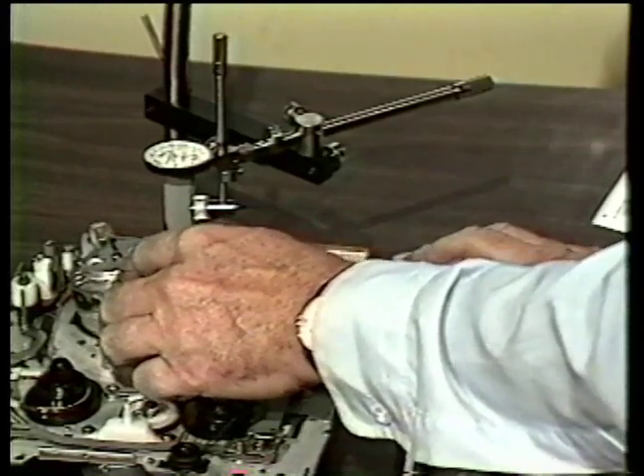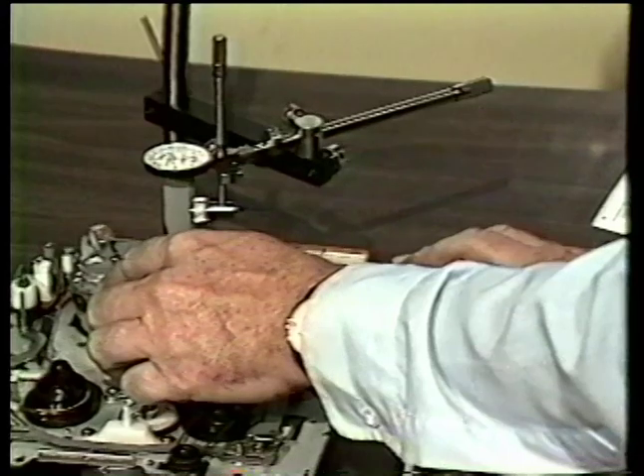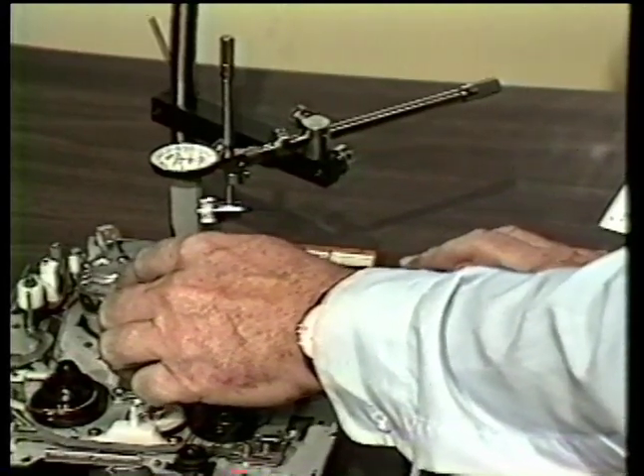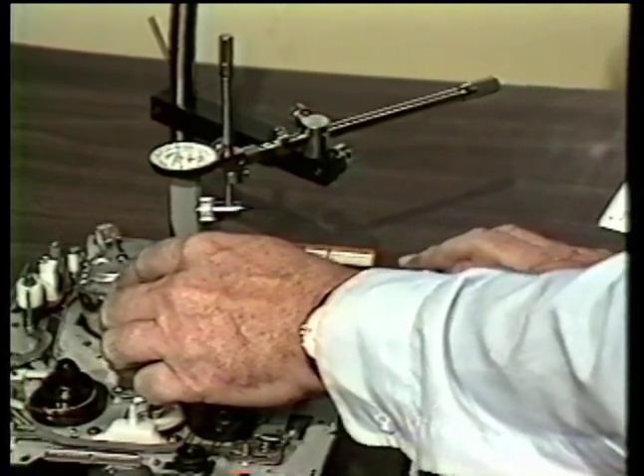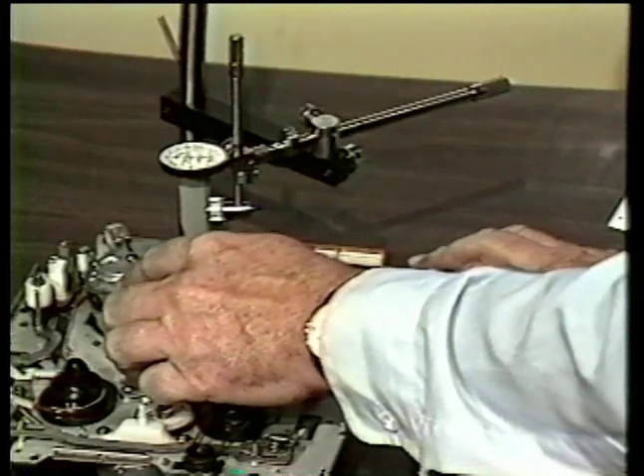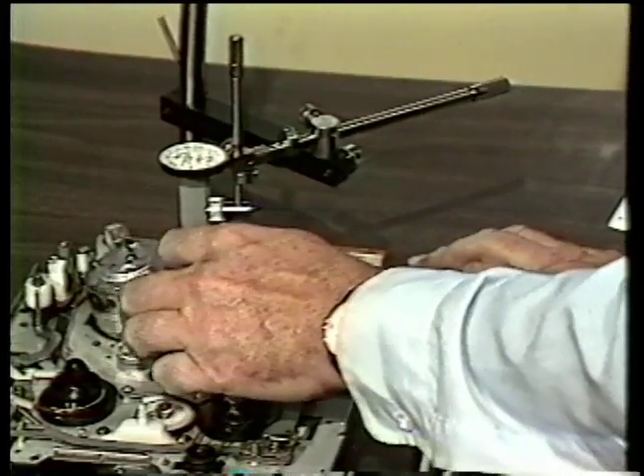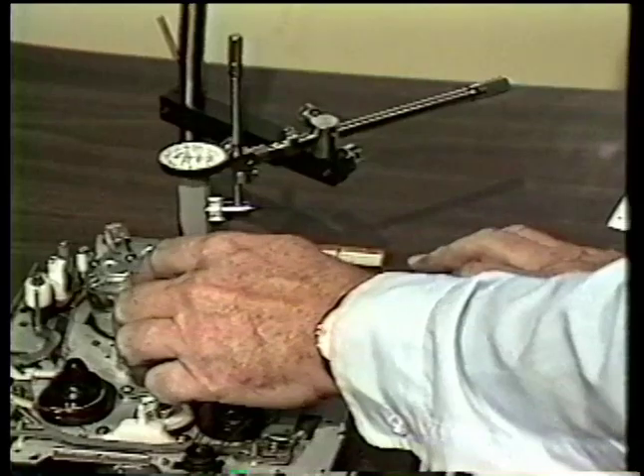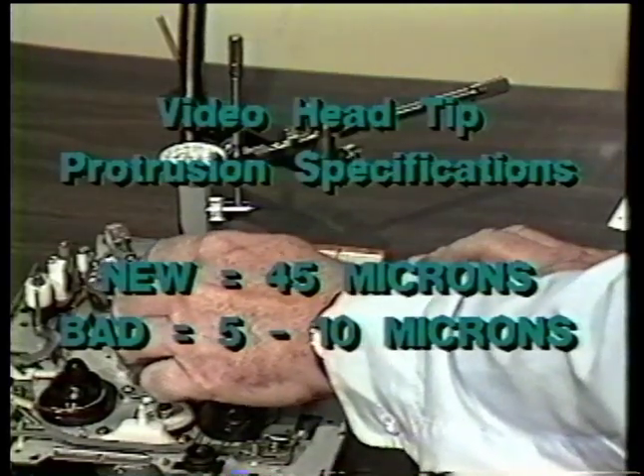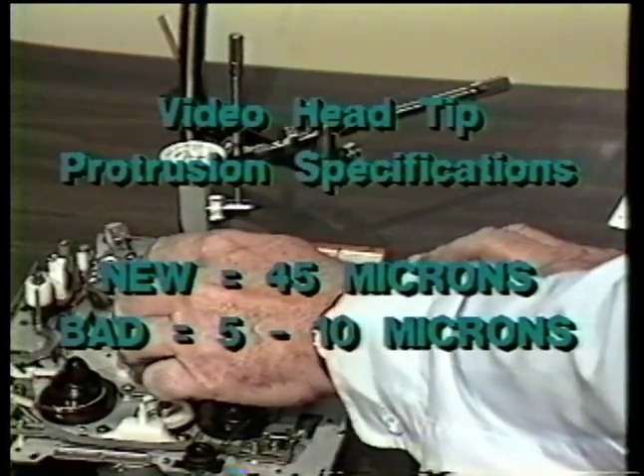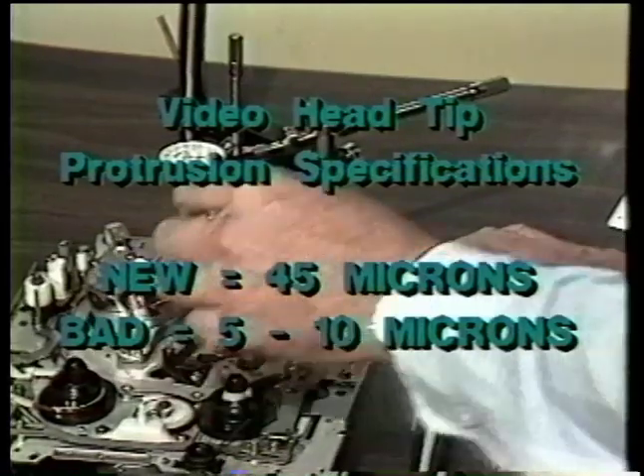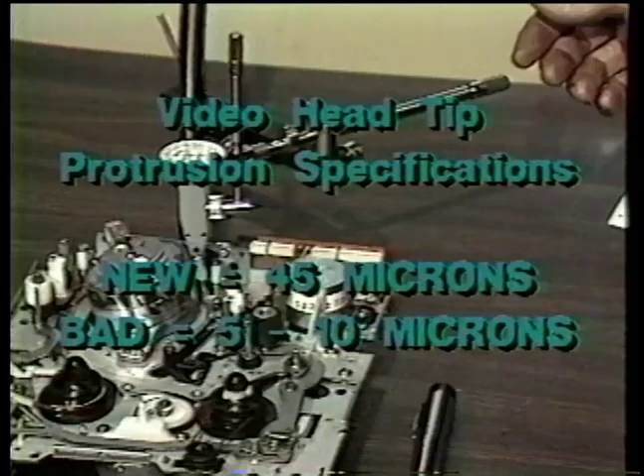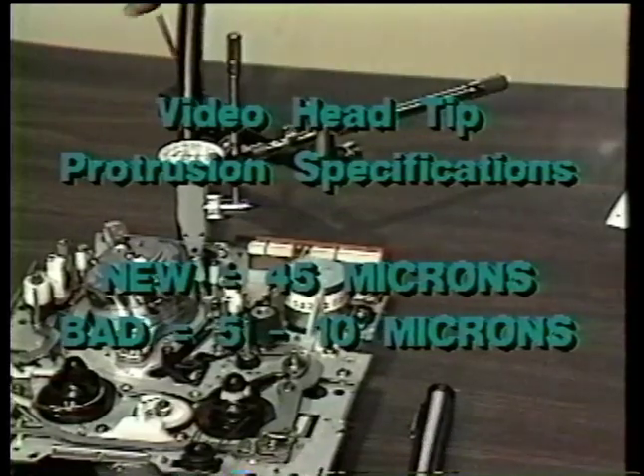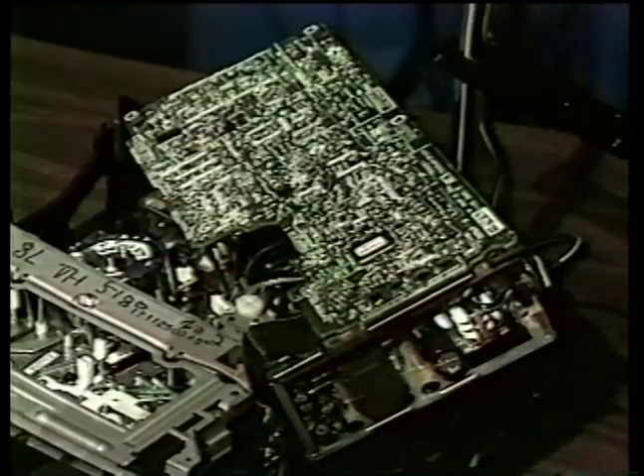So right now I'm at about 3 microns with a head tip under it. This one only goes up to about 13 microns. So it shows that these heads are in fact worn. We only have about 10 microns of protrusion. Okay, we've shown the setup of the head protrusion gauge on the bare chassis.